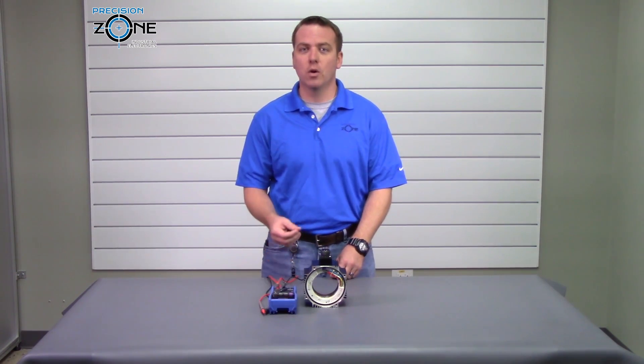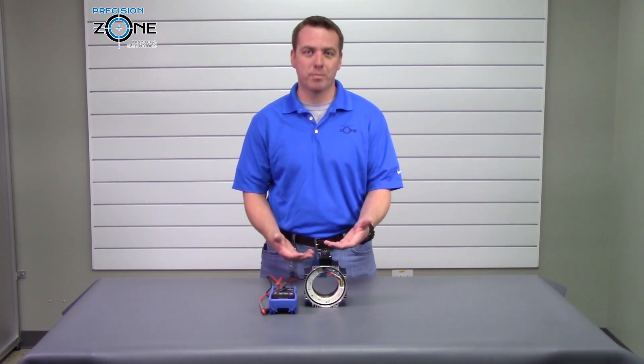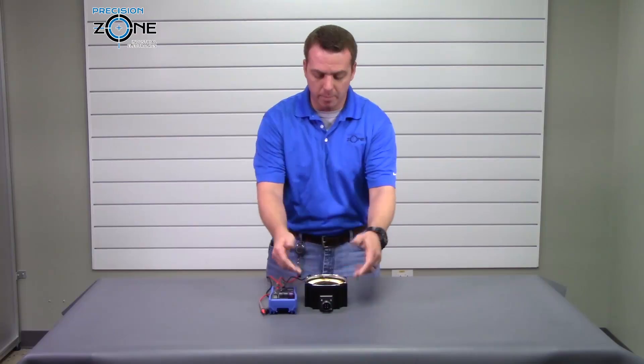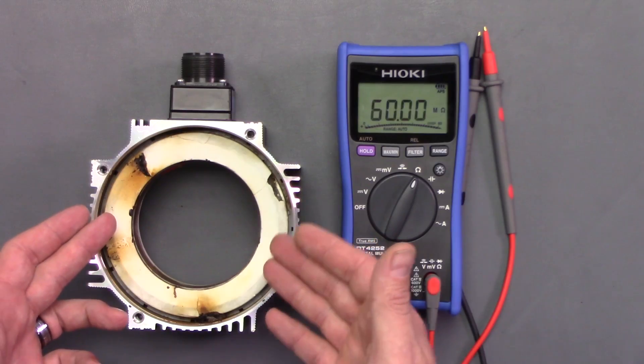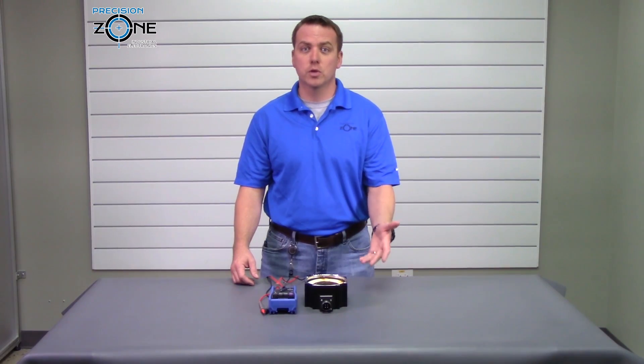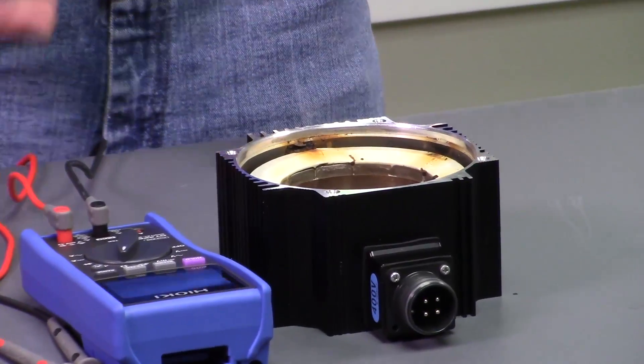And these two tests can only tell you if they have a big problem just like this stator. This stator has a burned-up winding and when you send your motor in we use our SKF Baker to find big problems like this one and also small ones that can cause you a big headache.